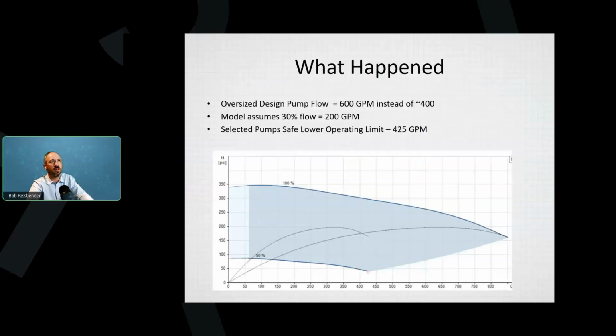And here's the pump selection. In gray or blue, you can see that the pump is supposed to operate in those areas. And the little red dot at the bottom there, I don't know if it's showing my cursor or not, the little red dot at the bottom is the point that they operated at. So they operated it at the safest and the lowest head that the pump was selected for. And that only got it down to 425 GPM, give or take. So the oversized model assumed 200 GPM. It was really supposed to run at 400 GPM. It ended up running all the time at 425 GPM. And the cost difference on that was about tenfold.